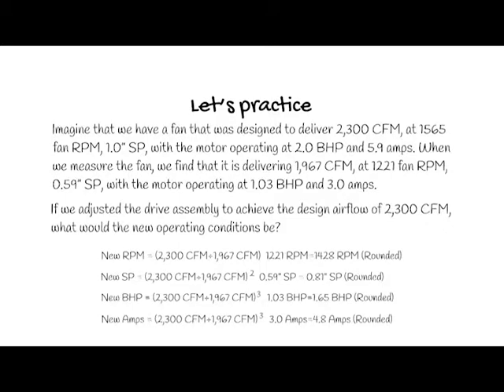So let's take a look at how we got these new numbers. First, we'll look at RPM. We used fan law 1 to calculate the new RPM. We took 2,300 — the new CFM — divided by the original CFM of 1,967. We multiplied that number by 1,221 RPM, which gives us 1,428 RPM.